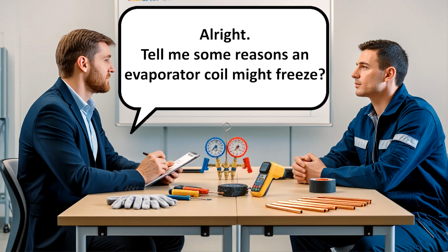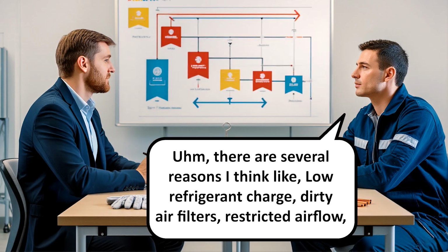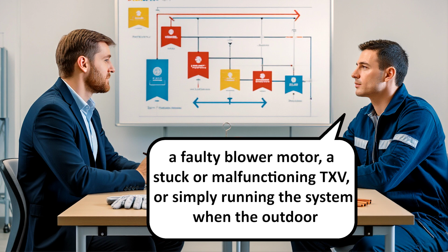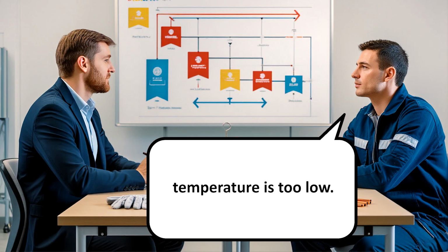All right. Tell me some reasons an evaporator coil might freeze. There are several reasons, I think, like low refrigerant charge, dirty air filters, restricted airflow, a faulty blower motor, a stuck or malfunctioning TXV, or simply running the system when the outdoor temperature is too low.